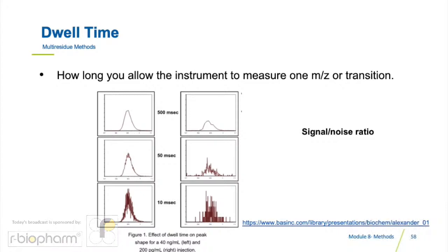Circling back to the dwell time, this is a value that can vary between instruments, but generally not by an order of magnitude. Using round numbers for illustrative purposes, an analyte may produce a signal-to-noise ratio of 3:1 with 10 millisecond dwell time. This would be the absolute minimum dwell time to use to make a screening measurement, which needs a signal-to-noise of 3 or more.